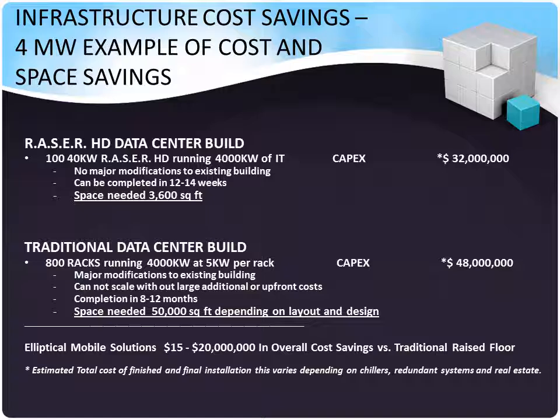Infrastructure cost savings in this 4-megawatt example are significant when using our micromodular data centers. We have 100 40-kilowatt R.A.S.E.R. HD units running 4,000 kilowatts of critical IT load for a total cost of $32 million with no major modifications to the existing building. It can be completed in 12 to 14 weeks and you only need 3,600 square feet. Traditional data center builds would require 800 racks at $48 million, all paid up front, with major modifications to the existing building. It will not scale to meet your business need, can take up to a year to complete, and takes about 50,000 square feet.